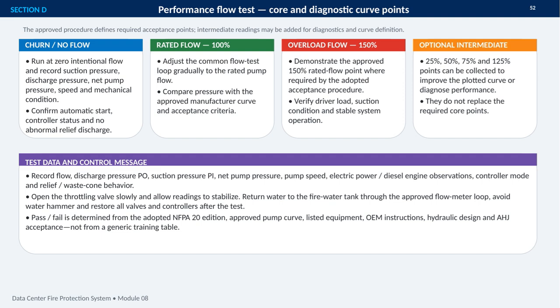At rated flow, I gradually adjust the common test loop to 100% of rated pump flow, then compare the measured pressure with the approved manufacturer curve and acceptance criteria. Where required, I also demonstrate the 150% overload flow point, checking driver load, suction conditions, and stable operation. Optional readings at 25, 50, 75, and 125% can improve the plotted curve, but they do not replace the required core points.